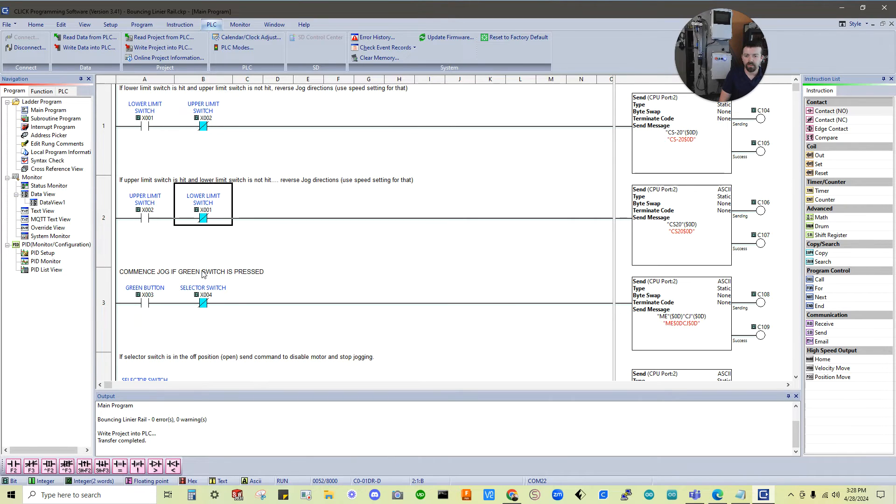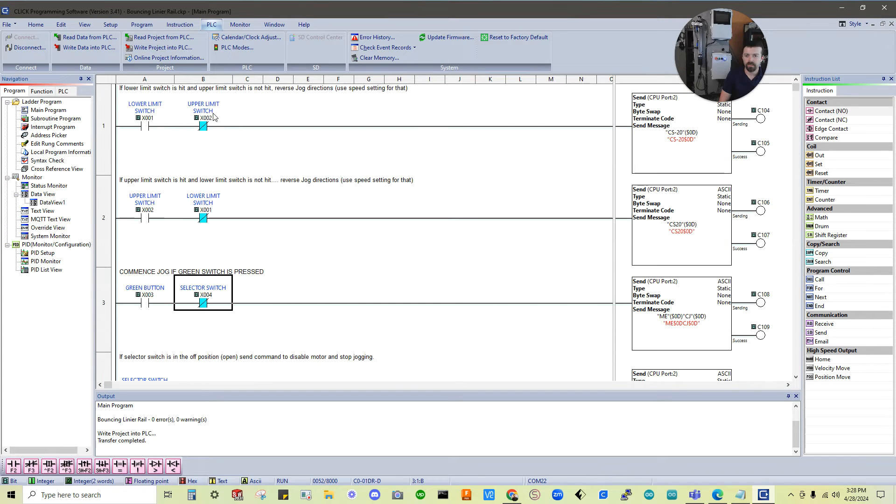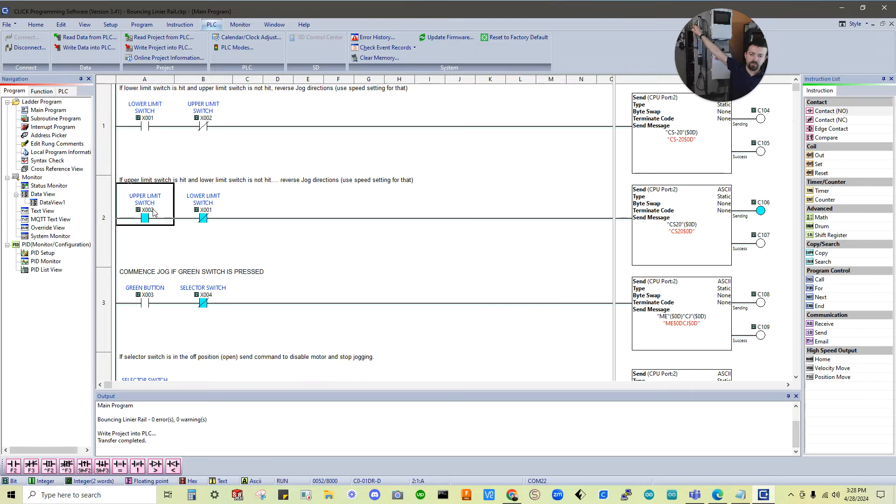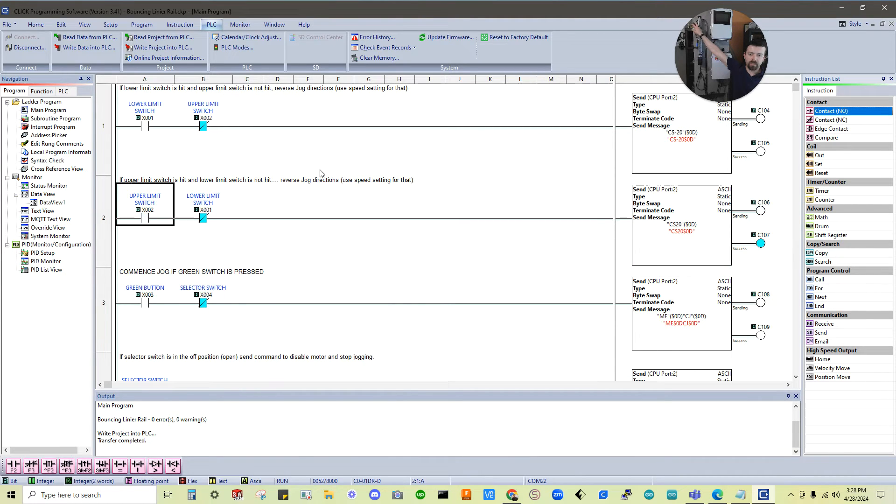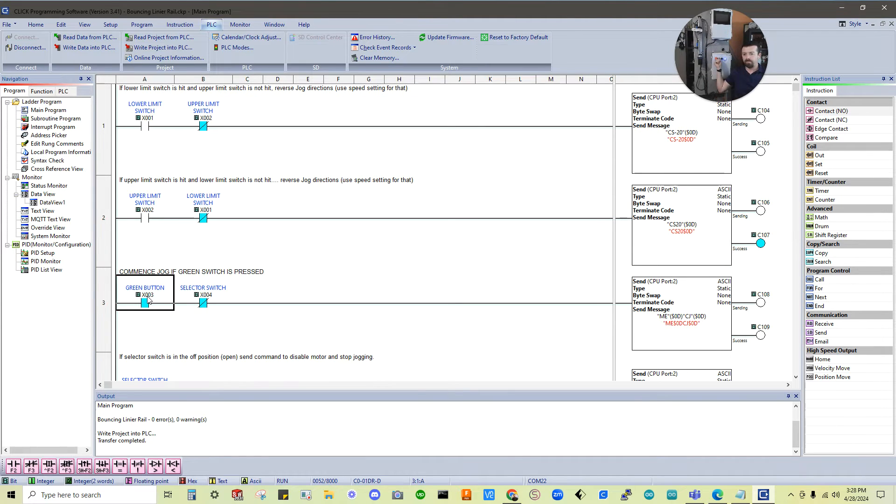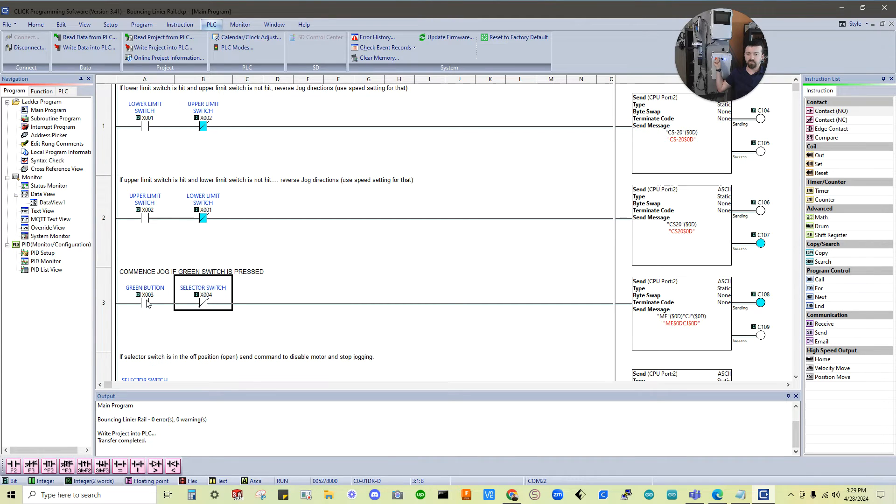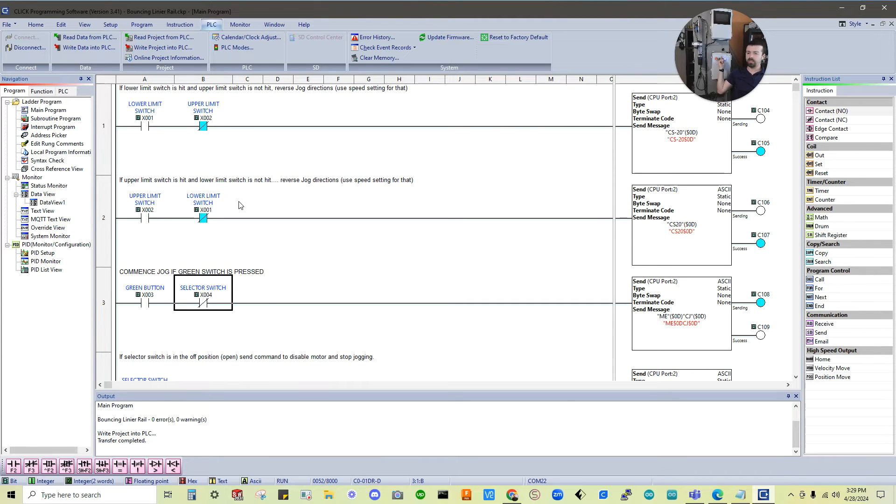And you see now that I've gotten highlighted icons here, and that I can see reactions. So this is the upper limit switch. And if I engage it or disengage it, you can see those changes happening. There's also the upper limit switch indicator. This is a normally closed contact. This is a normally open contact. You can see both symbols there. You can see them behaving and indicating based on what they are. Cool. I also have the green button here. And we have the selector switch here. You can see based on those. So I can leave the selector switch in the off position. Select green. This is how you would do your basic checks. Make sure you've wired everything right. But cool. They should be behaving like this.